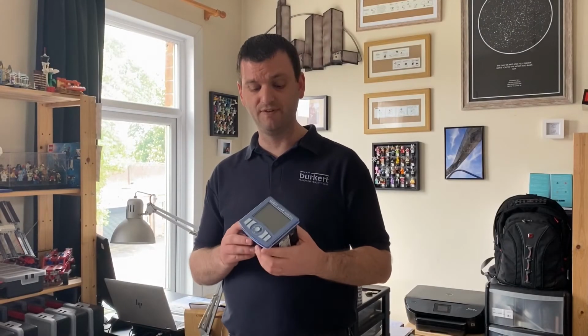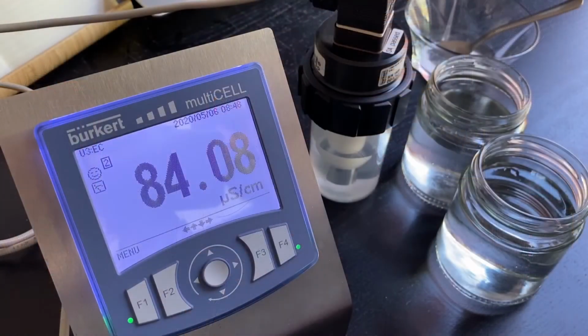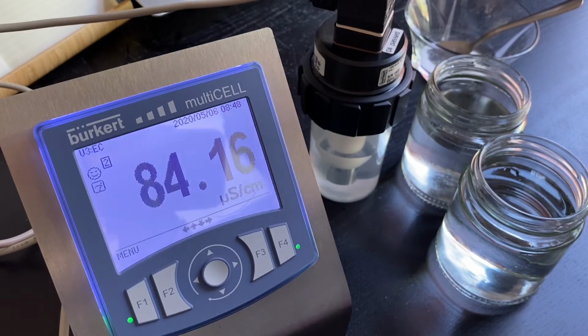Now the Multicell that I have here today is an old demonstration device and doesn't have any advanced PID functionalities. But what I can do is show you the screen, show you some of the menus, along with one of the conductivity sensors that I have here. As you can see on screen now, we've got the Type 8619 Multicell connected to one of our conductivity sensors, the Type 8220. We've just got a very clear measurement of 84 microsiemens. This is currently sat in a calibration solution. It's quite an old probe, so I would expect a little bit of drift, but it's not too bad.